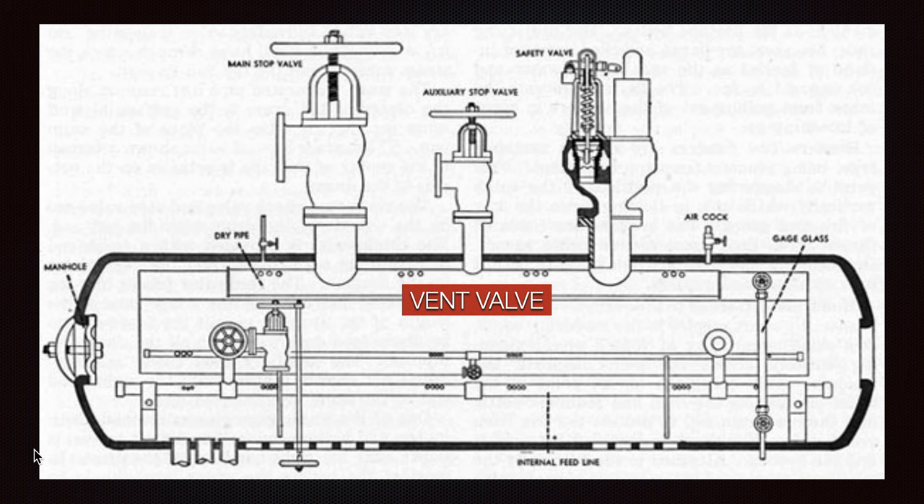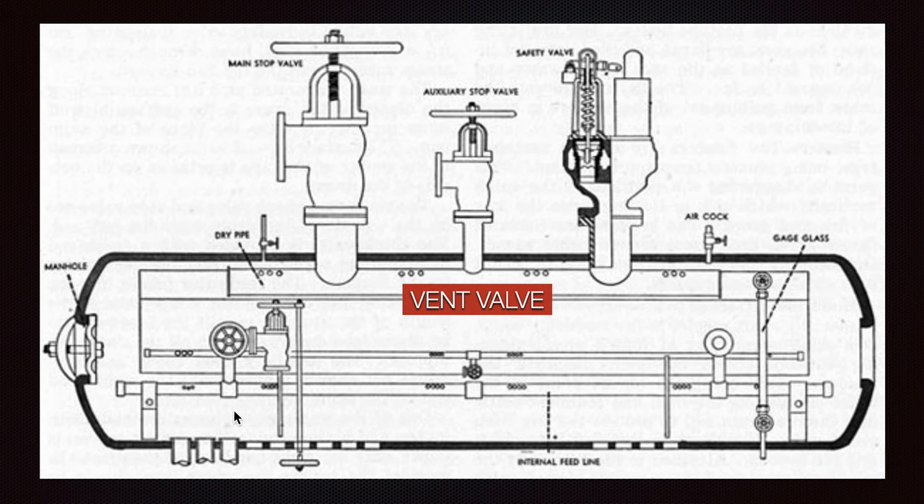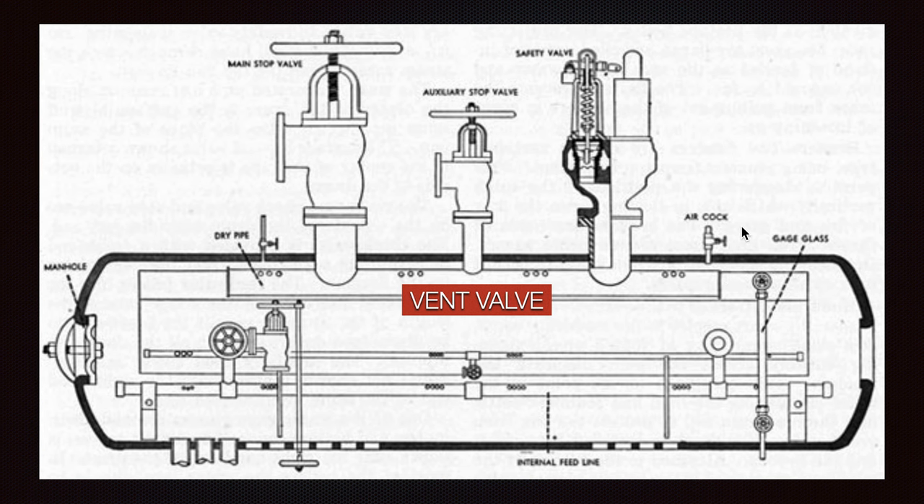Next we have the vent valves and the air cock, which must be opened when depressurizing the boiler and during the initial start when we step up and increase the boiler pressure. As you can see, there is a dry pipe so whatever water is accumulated will be collected here and dropped back to the top part of the boiler where steam production occurs.